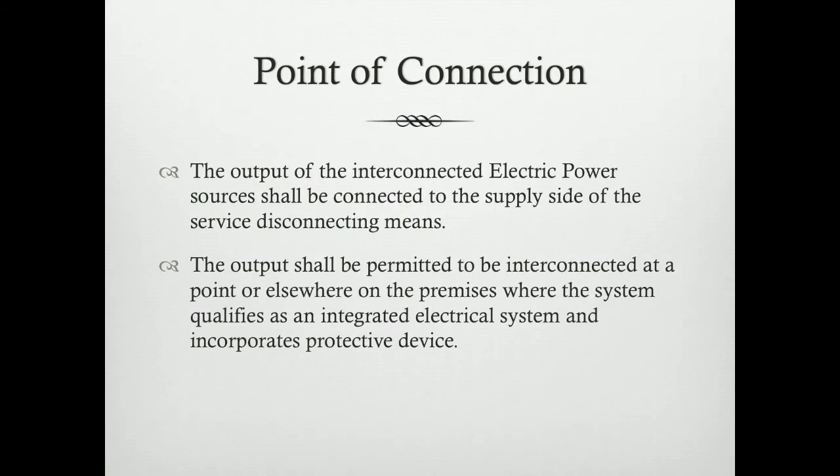The point of connection of the interconnected electrical power source shall be connected to the supply side of the service. The output shall be permitted to be interconnected at a point or elsewhere on the premises where the system qualifies as an integrated electrical system and incorporates a protective device. The conductor sizing should be appropriate so that when it is tapped into the system, it does not create any form of hazard. That is why there must be a person qualified and competent to do this kind of work.